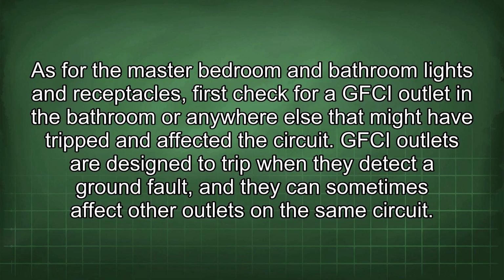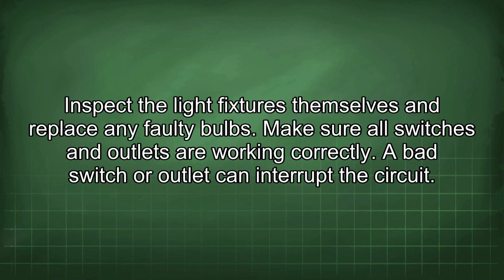As for the master bedroom and bathroom lights and receptacles, first check for GFCI outlets in the bathroom or anywhere else that might have tripped and affected the circuit. GFCI outlets are designed to trip when they detect a ground fault, and they can sometimes affect other outlets on the same circuit. Inspect the light fixtures themselves and replace any faulty bulbs. Make sure all switches and outlets are working correctly. A bad switch or outlet can interrupt the circuit.